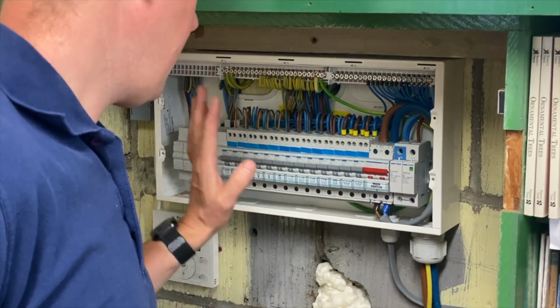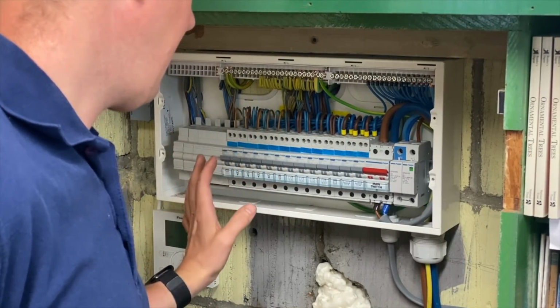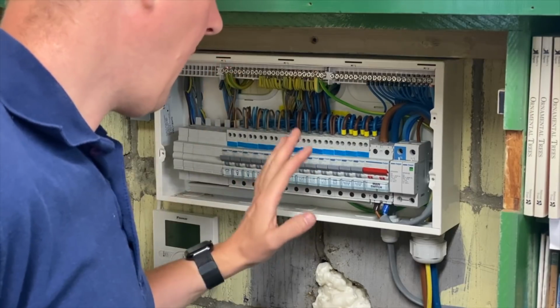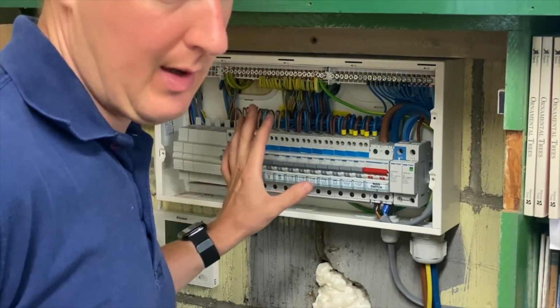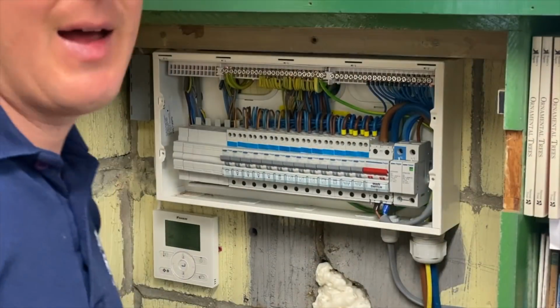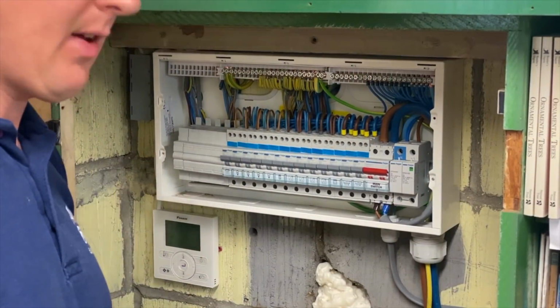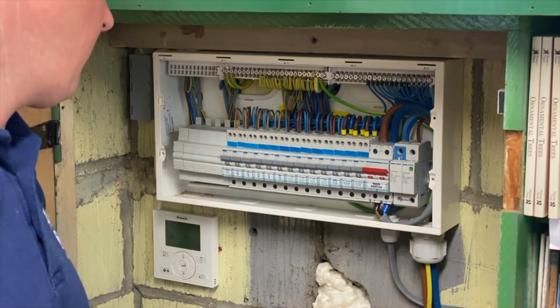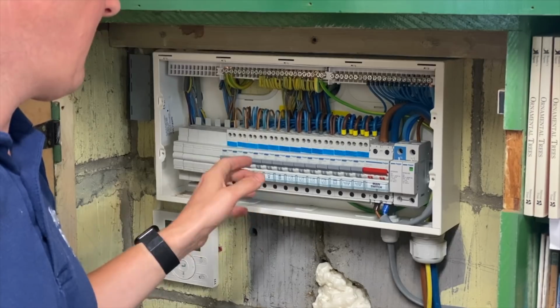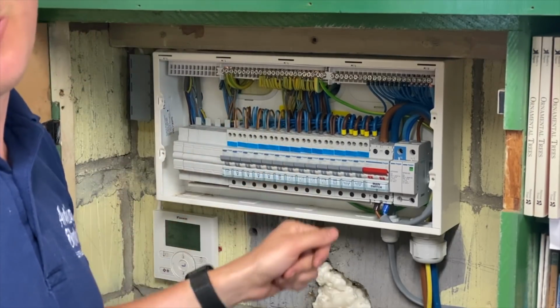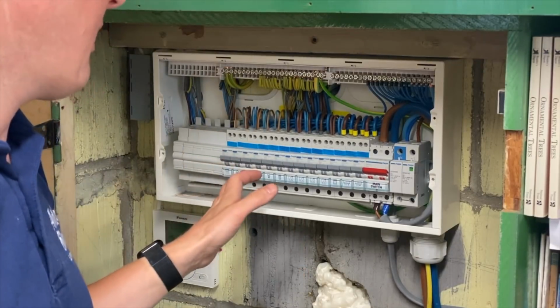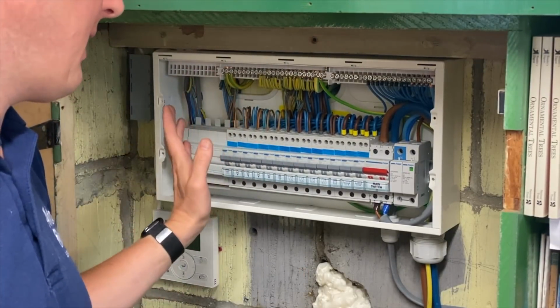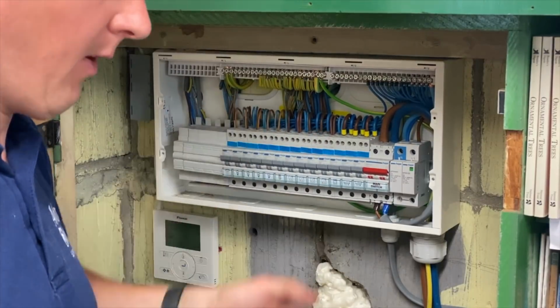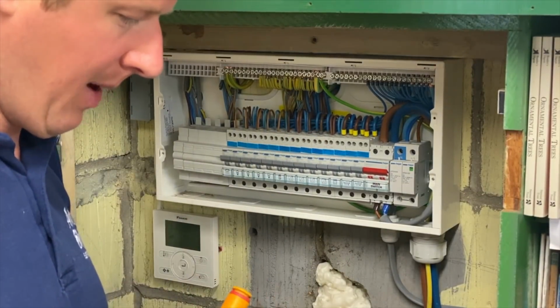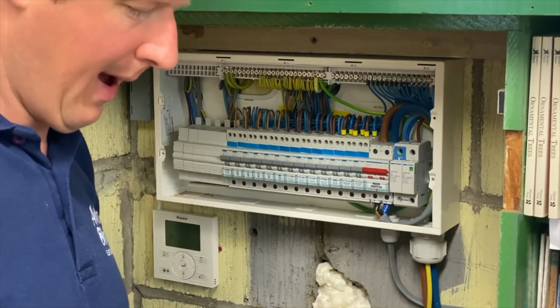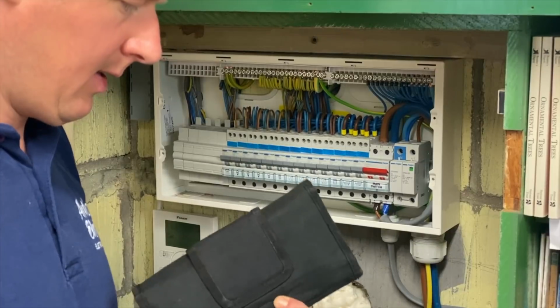So now that all the connections are kind of done, we're not going to be removing anything or putting anything back, I'm going to torque up all these screws now. That's really important to make sure that they're all tightened to the correct torque setting. As I mentioned when I did the consumer unit installation video, when I first do the installation I just tighten them up hand tight, shall we say, not tight as they should be, but tight enough to provide a secure connection. And then at the end, once I've finished testing everything, I go through it and do the final torque tests. It's not going to make any difference to the readings, but it's more about the mechanical soundness of the terminations.